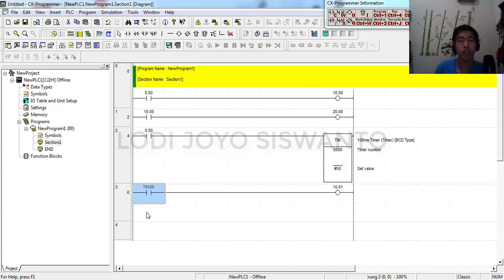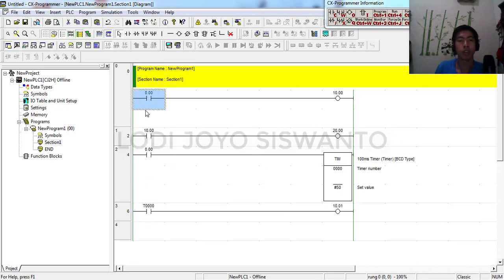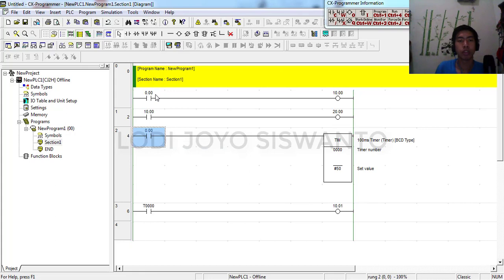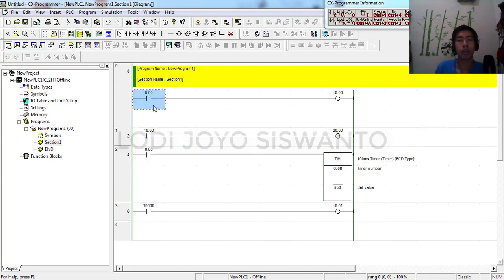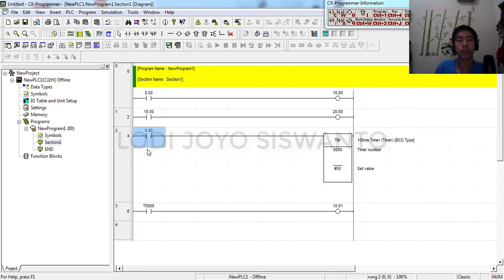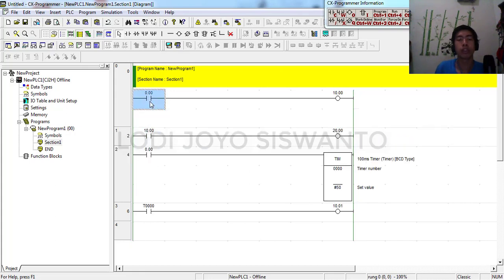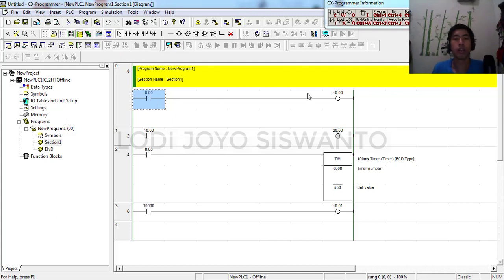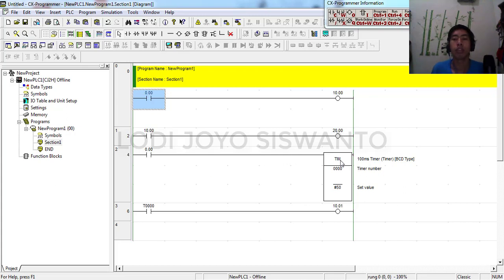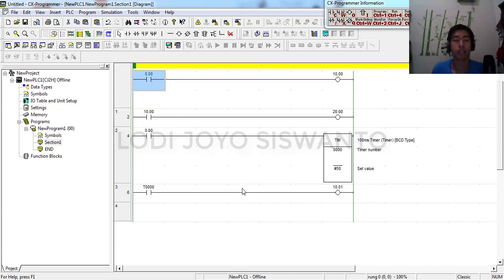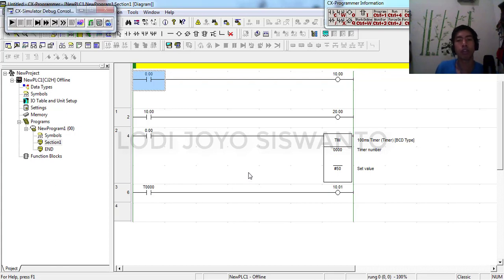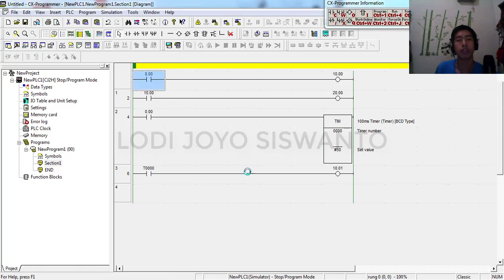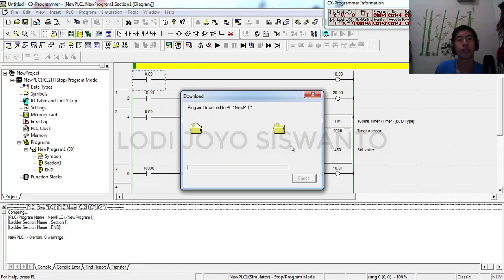In here we have the step address, and the same address gives logic one to coil 10 bit 0 and gives logic one to timer 0. And we can simulate, please push Ctrl Shift plus W. And Control G for force on. The differentiation is this channel 10 bit 0 is directly on, and this channel 10 bit 1 is waiting, the timer value is 5 seconds like that.